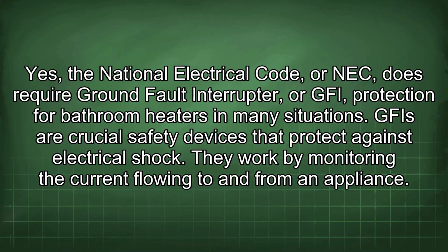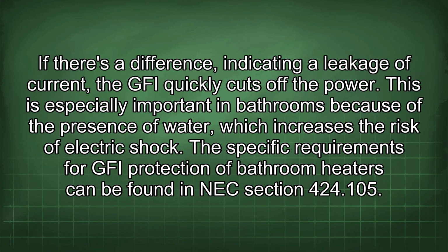Yes, the National Electrical Code, or NEC, does require ground fault interrupter, or GFI, protection for bathroom heaters in many situations. GFIs are crucial safety devices that protect against electrical shock. They work by monitoring the current flowing to and from an appliance. If there's a difference, indicating a leakage of current, the GFI quickly cuts off the power. This is especially important in bathrooms because of the presence of water, which increases the risk of electric shock.